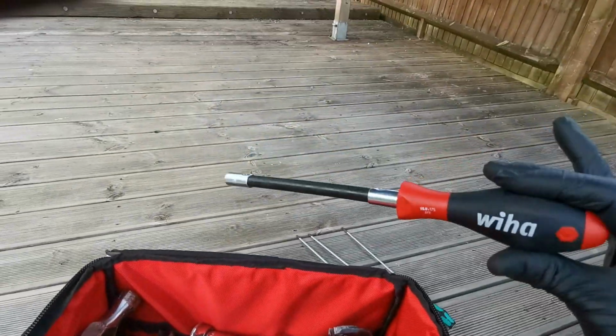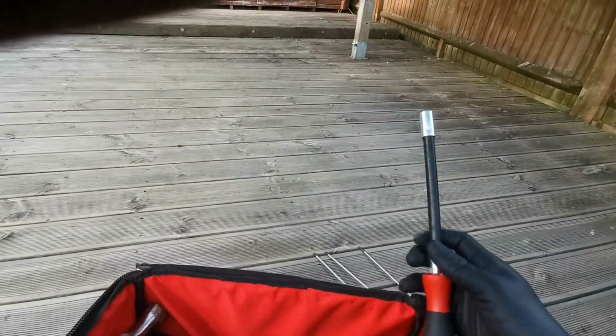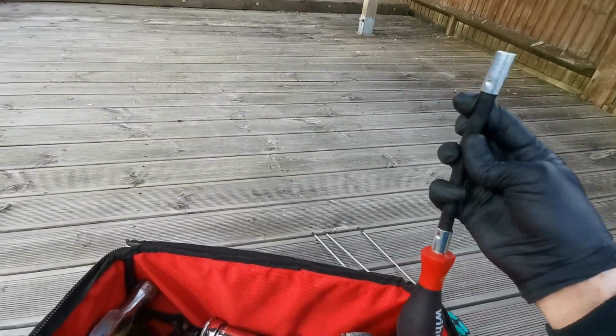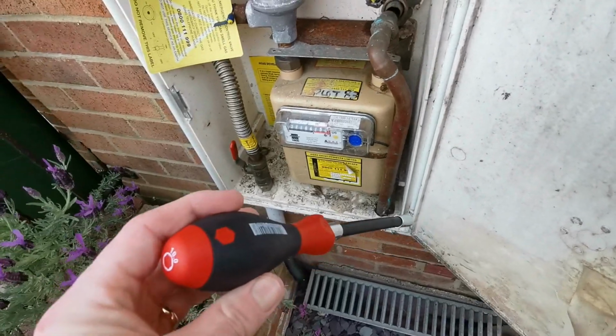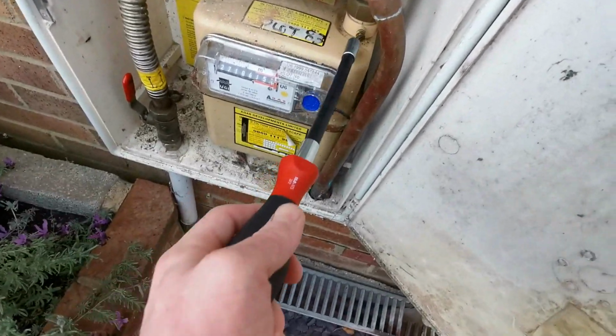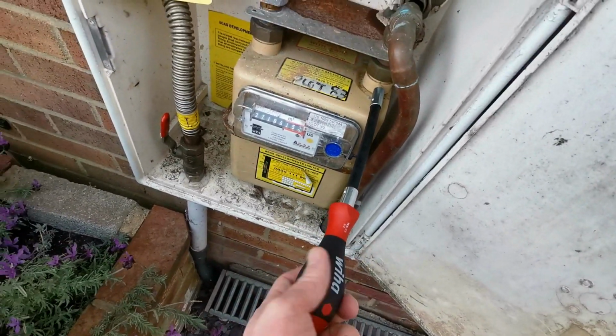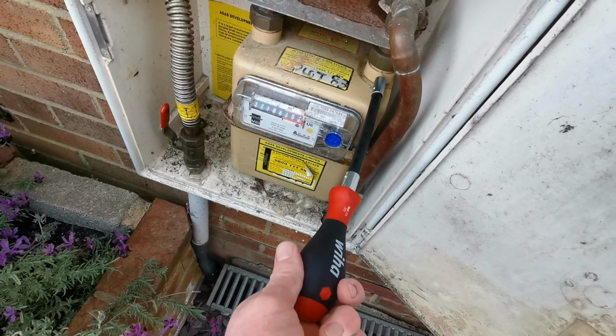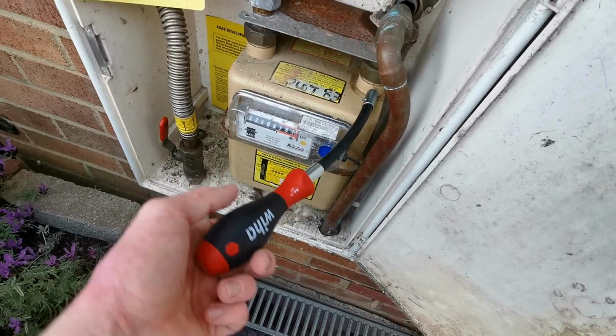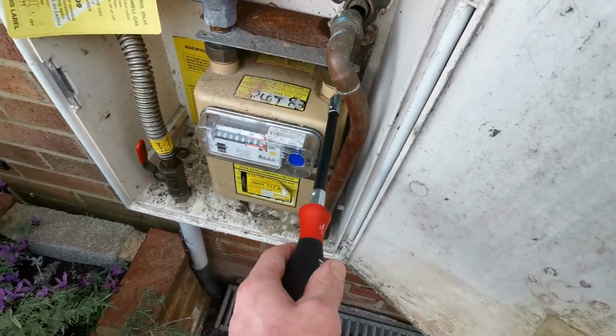Start in the centre of the bag, got my analyzer wrapped in a dust sheet, kneeling pad, my Wera ratchet set, then I've got a Wera flexi shaft 10mm driver which does the gas meter test nipples with ease. If there's any rigid pipe work in the way, that just flexes right around it. The semi-concealed ones in the ground, sometimes you can't get your screwdriver in there, that just flexes in there nicely. One tool does all the gas test nipples, perfect.